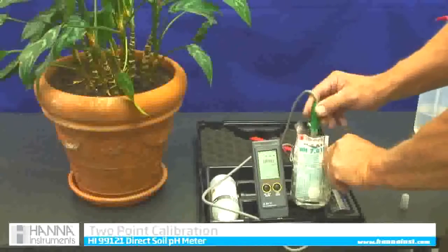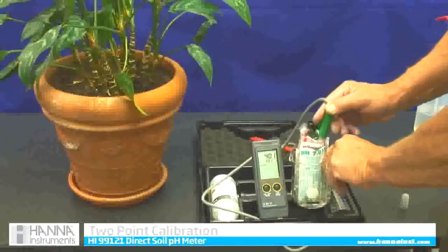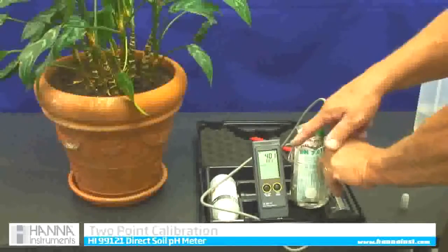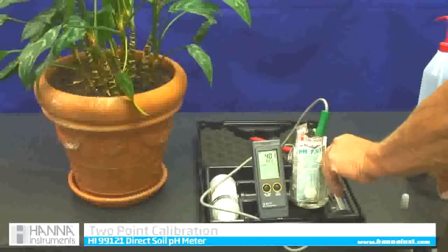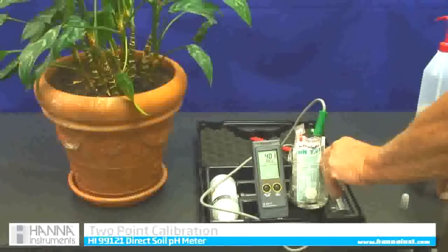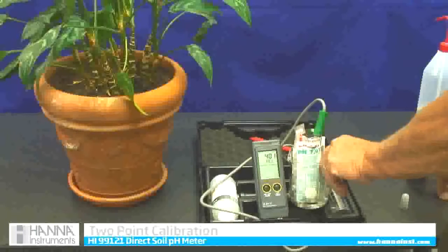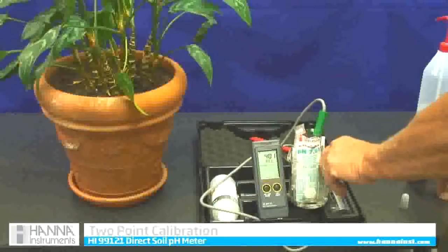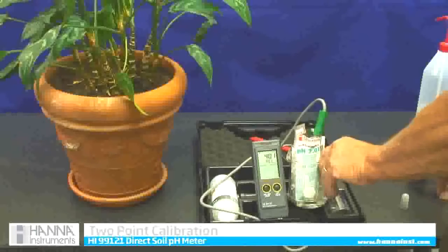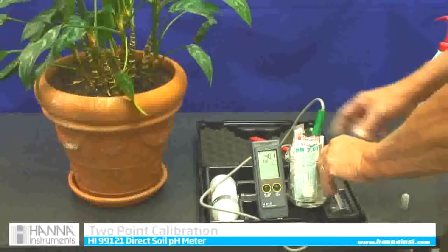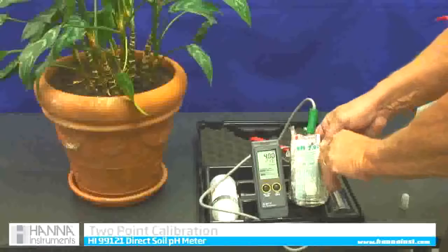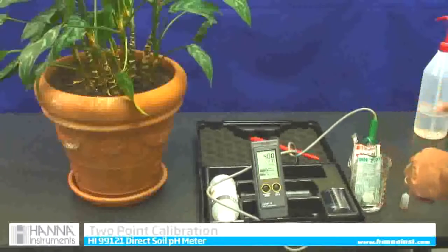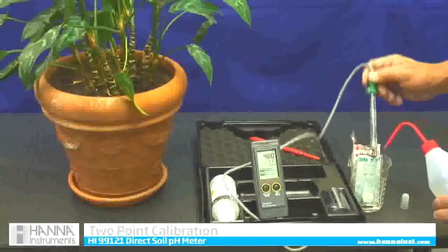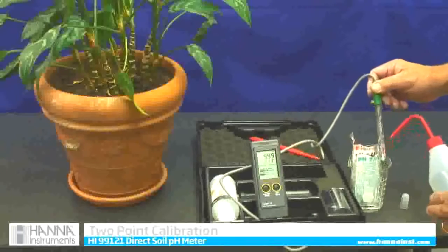And then it's going to say use 4.01. Now I put it in 4.01 and it recognizes that. I could use a 10. It would recognize a 10.01 if you wanted to, but in agriculture we use the 7 and 4 two-point calibration. Makes it very accurate. All right, now I'm okay. If you can read it, it says okay 2 points. I am just going to then rinse it off with a little bit of clean water.